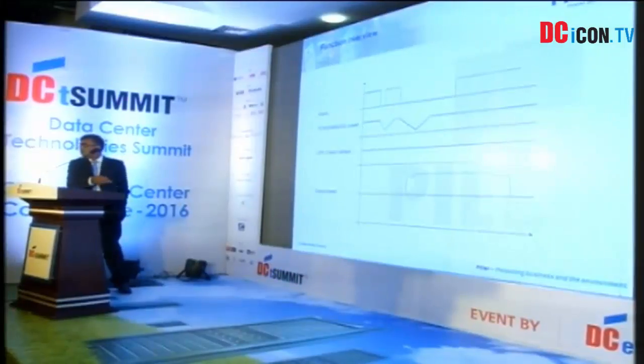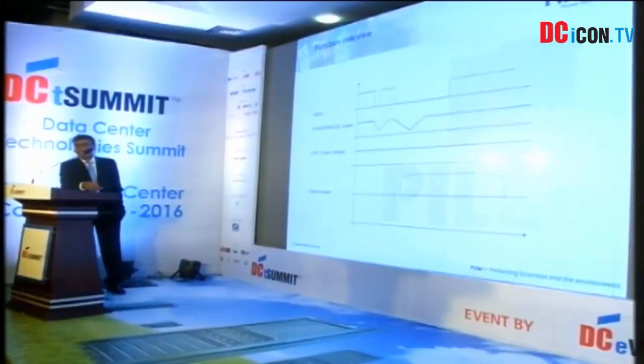This is a time chart of how the operation of this diesel rotary UPS happens. So this is your mains. You have a disturbing mains. Either it could be a very short-term failure or a slightly longer failure. And this is the flywheel speed, the UPS output voltage, and the diesel speed. Two things that you have to note here.